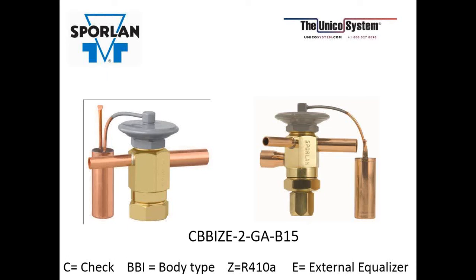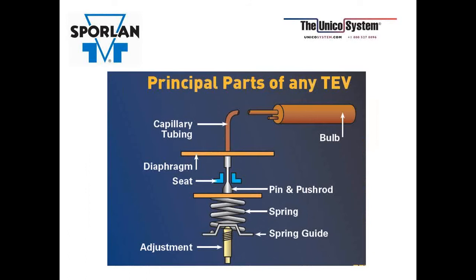The principal parts of any TEV: the diaphragm, capillary tubing, and bulb all can make up the thermostatic element. You have a seat, whether it's a drilled passageway or a screwed-in seat. Push rods, sometimes 2 push rods. In this case, this is a balanced port. It has a single push rod, and the push rod and the pin are a combination. You have a spring, superheat spring, spring guide, and if it's adjustable, you have an adjustment stem.